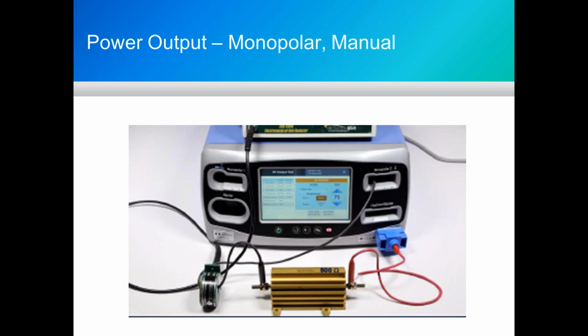Any inductance, any capacitance that is part of your measurement circuit, either internal in the analyzer itself or with external leads, can have a tremendous impact on your measurements, and to the point where if you're not careful, you can think a unit is out of calibration because of increased inductance and capacitance. You can make yourself go through the process of doing a calibration, and the concern always is then, are you actually adjusting it out of calibration or not? Think back to that screen that we were looking at. One of the things you can take a peek at when you're doing a power test is what the impedance that the FT10 is sharing with you that it's seeing, and that impedance again is the DC resistance influenced by inductance and capacitance.